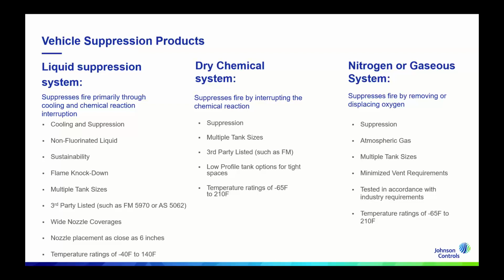And another option, right, is the nitrogen or gaseous systems. And these types of systems suppress fire by removing or displacing oxygen. Similar to what we talked about on the liquid system, right? Nitrogen removes oxygen from the formula that we saw at the beginning. By removing one of those 4 elements, we're able to suppress fire. Nitrogen is used specifically for suppression.